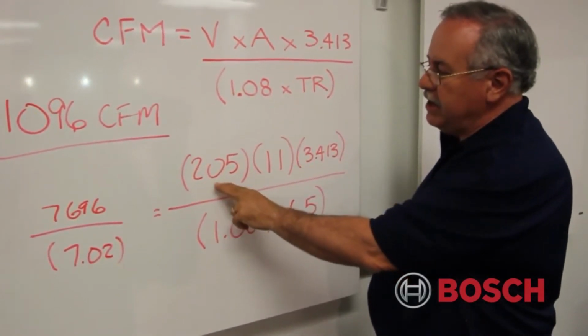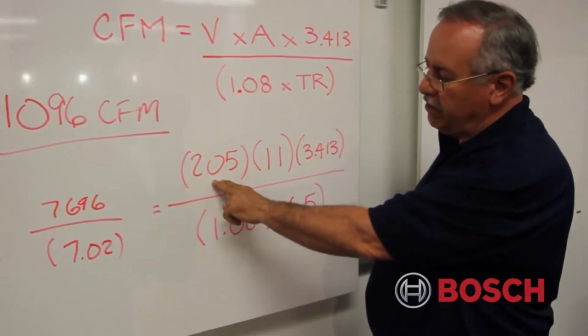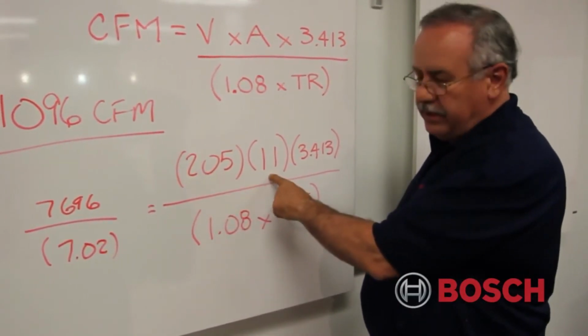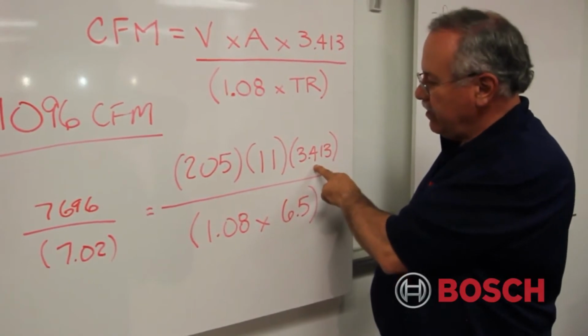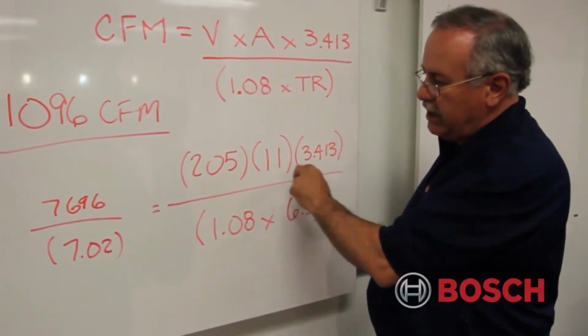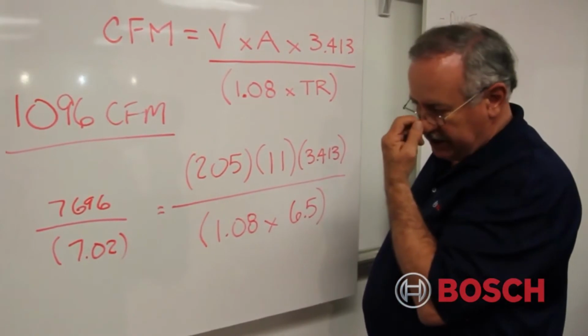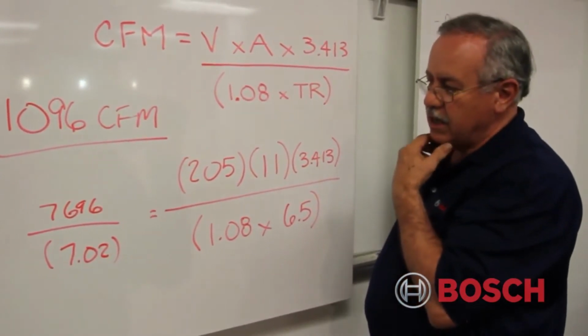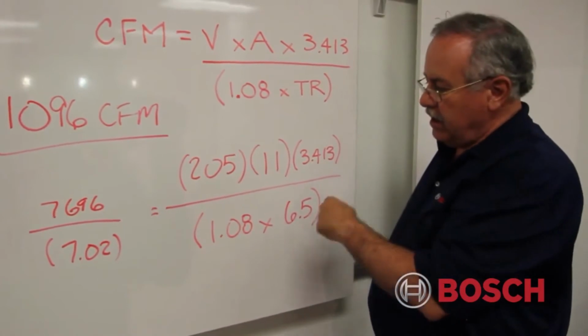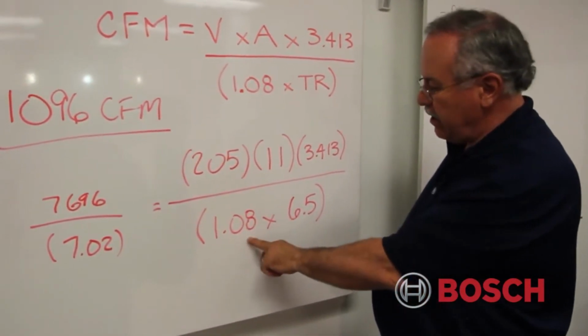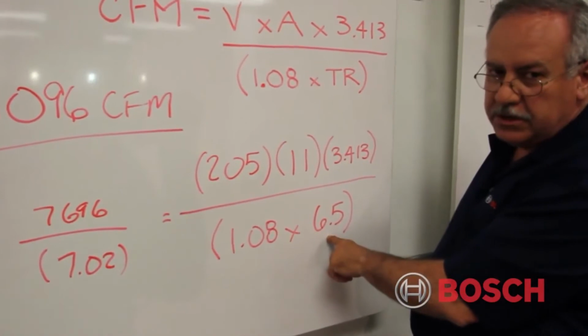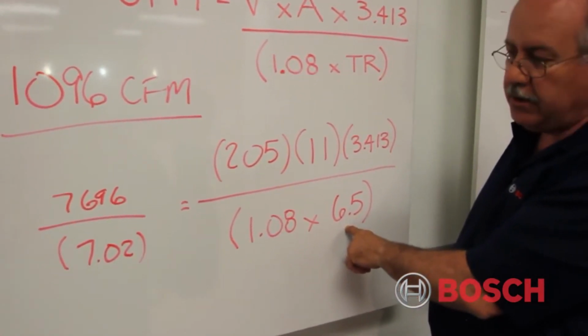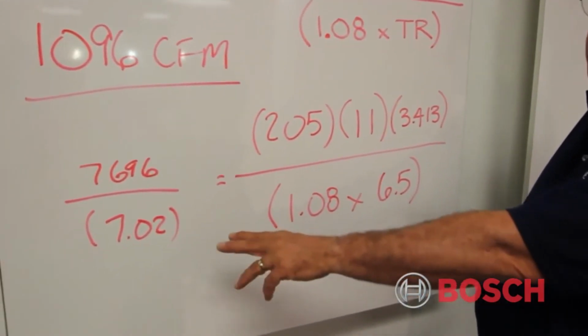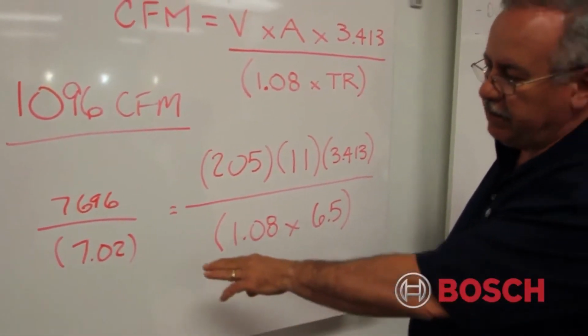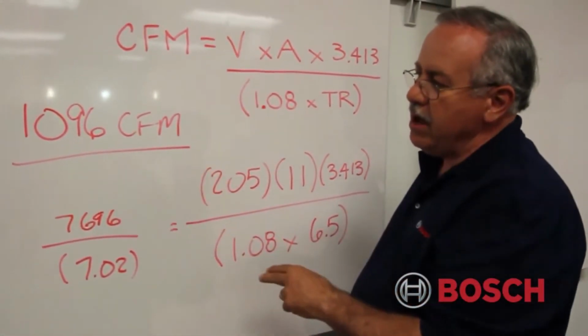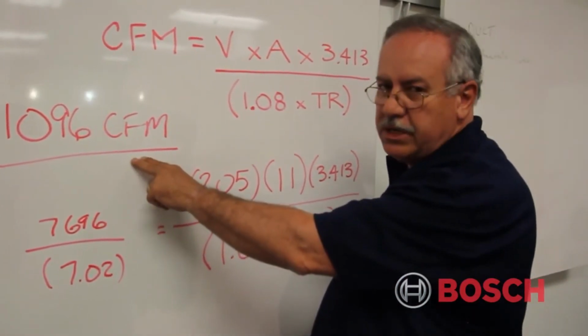So if I insert the values we found, we saw around 205 volts, approximately 11 amps, and we convert it with 3.413 BTUs per watt, and that gives us approximately 7,696 BTUs coming across that energized heater. Then we multiply 1.08, our constant, times around 6.5, which is our difference in temperature we saw between supply and return. That gives us 7.02. So 7696 divided by 7.02 is around 1096, or close to 1100 CFM.